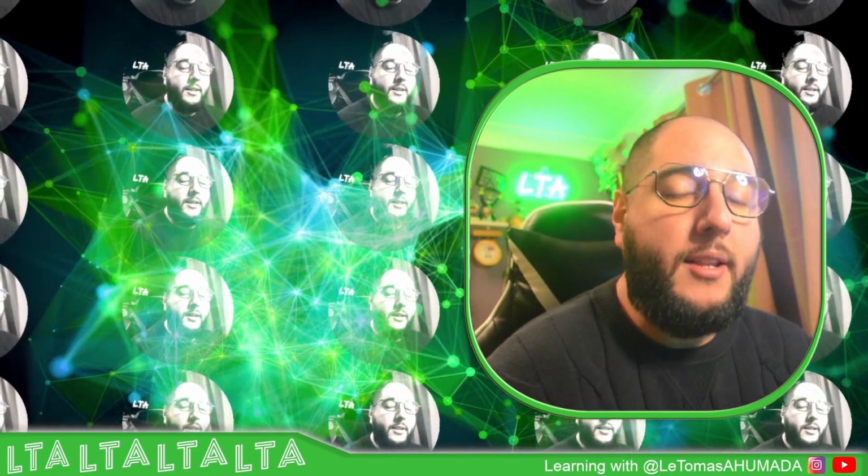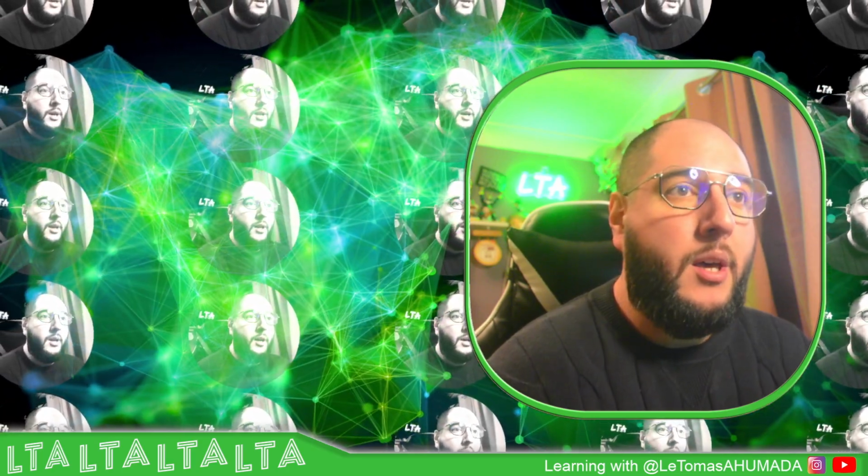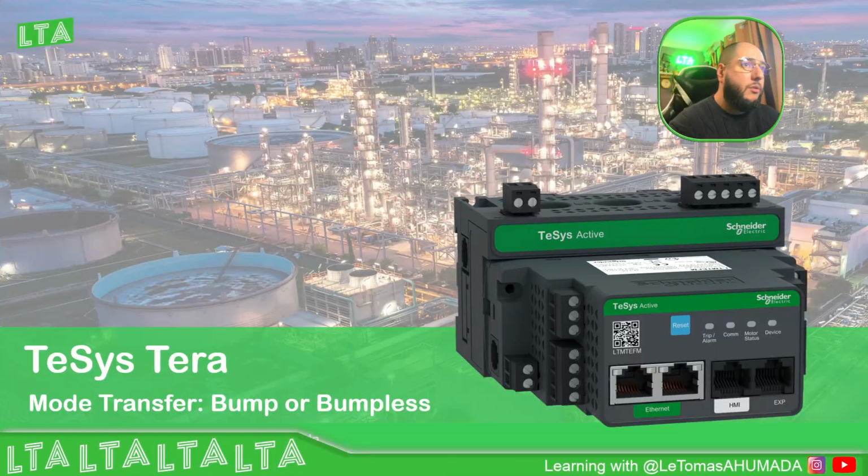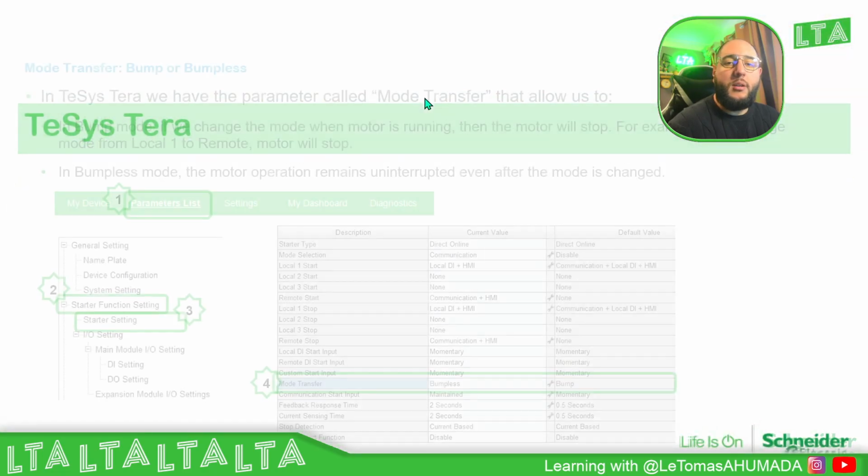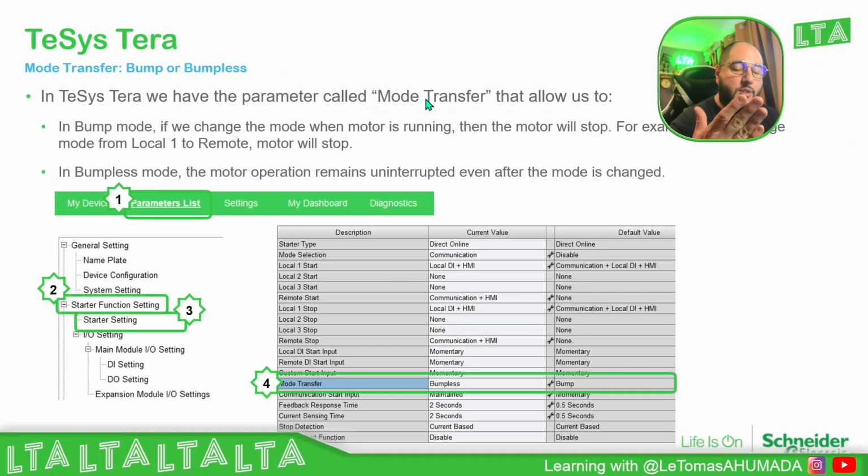I'm your host, Leandro Mata, and in this video what we're going to see is the mode transfer configuration that we have in TeSys Tera. So basically we have on this mode transfer the possibility to use bump and bumpless mode. If you're using bump, when you change the mode selection, for example, you are controlling for local DI and then you change for communication, when the motor is running, it will stop. If you're using bumpless and the motor is running, when you change, it will not change the status of the motor. That will be the main idea.